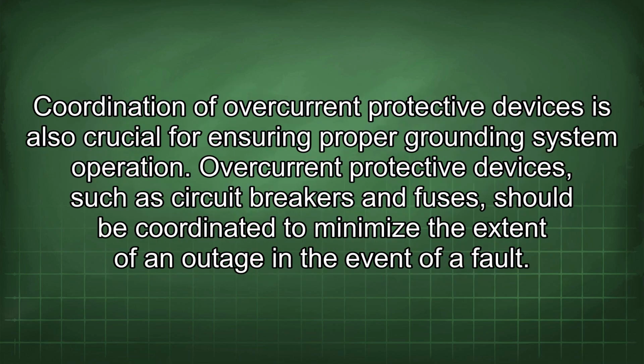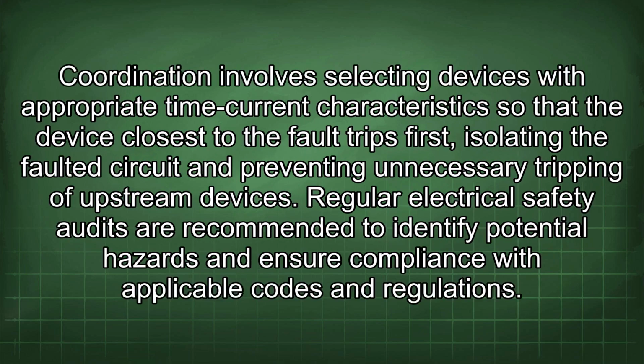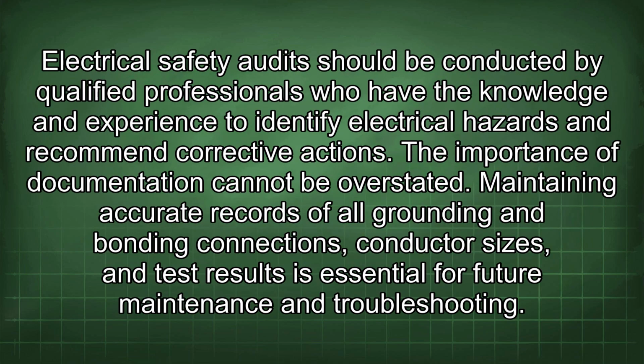Coordination of overcurrent protective devices is also crucial for ensuring proper grounding system operation. Overcurrent protective devices, such as circuit breakers and fuses, should be coordinated to minimize the extent of an outage in the event of a fault. Coordination involves selecting devices with appropriate time-current characteristics so that the device closest to the fault trips first, isolating the faulted circuit and preventing unnecessary tripping of upstream devices. Regular electrical safety audits are recommended to identify potential hazards and ensure compliance with applicable codes and regulations. Electrical safety audits should be conducted by qualified professionals who have the knowledge and experience to identify electrical hazards and recommend corrective actions. The importance of documentation cannot be overstated.